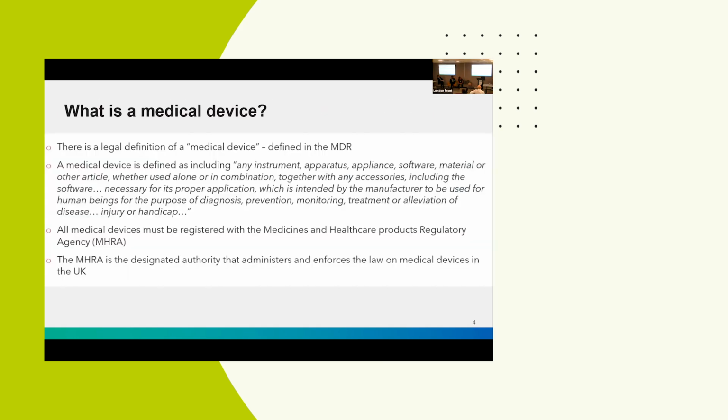So what is a medical device? This is a definition I've just picked up from the regulation. I'm not going to read it, but it's here to read. If the product you're manufacturing satisfies this definition, that is, it is a medical device, then you need to register it with the authority in this country, which is MHRA.